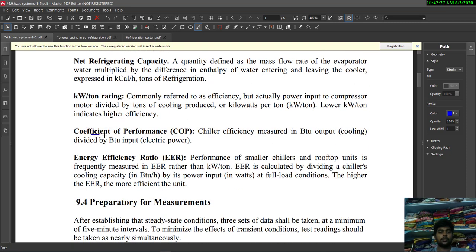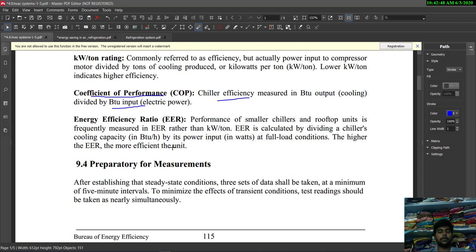Next is coefficient of performance (COP) — the performance of the cooling system or chiller efficiency, measured as BTU output divided by BTU input (electric power). It is the ratio of the cooling output to the electric power input.